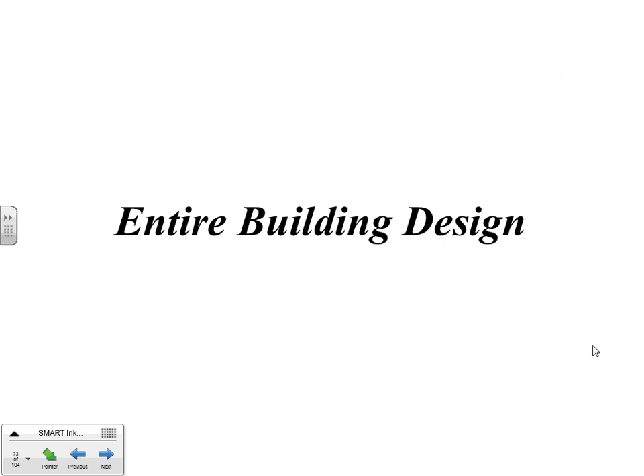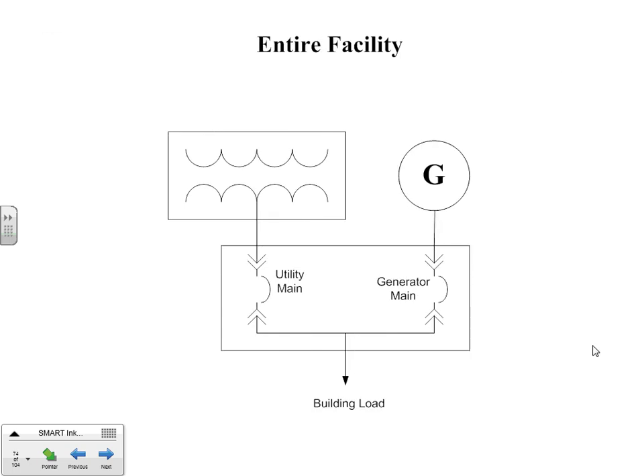In the entire building, back to this drawing again, we look at our soft load switch. In this situation, I drew this as very simplistic, but as Chad pointed out, this is now a service entrance device where we're taking over the entire facility. So this is a service entrance rated soft load switch here.